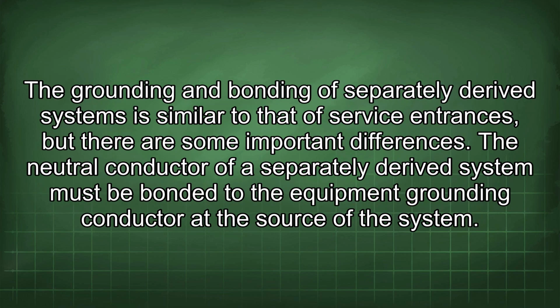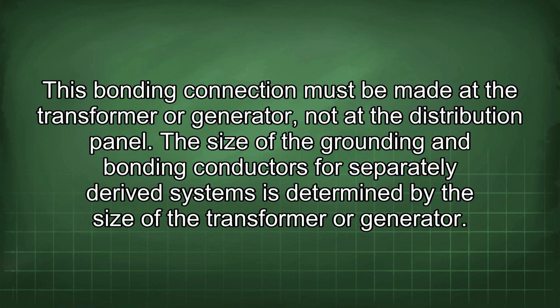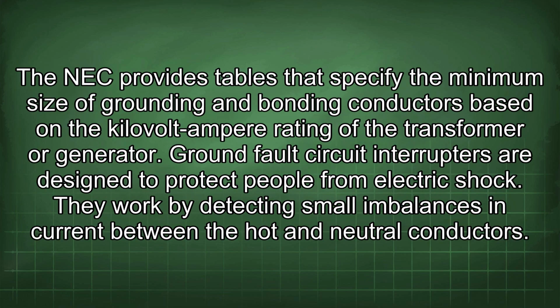The grounding and bonding of separately derived systems is similar to that of service entrances, but there are some important differences. The neutral conductor of a separately derived system must be bonded to the equipment grounding conductor at the source of the system. This bonding connection must be made at the transformer or generator, not at the distribution panel. The size of the grounding and bonding conductors for separately derived systems is determined by the size of the transformer or generator. The NEC provides tables that specify the minimum size of grounding and bonding conductors based on the kilovolt-ampere rating of the transformer or generator.